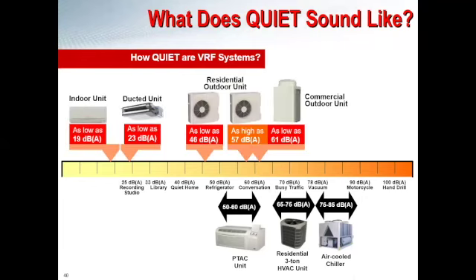And I'm not going to draw this out too much, but one thing that I really like to show is that the commercial outdoor unit in its single module, when it's running at 100% capacity, which we shouldn't be designing for, typically we want them to run somewhere between 50 and 75%, is going to be about as loud as your standard PTAC. So the parallel to draw is most people are okay sleeping with that PTAC in a hotel room. That's as loud as your outdoor unit is going to be. So that's why you can install those inside without any sound issues, without any vibration issues, anything like that. As you can see, as the condensing units get smaller, they get quieter.